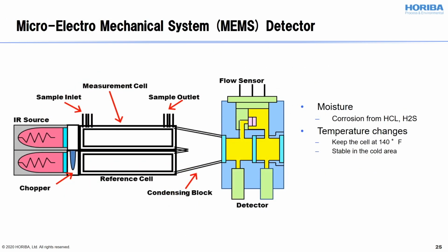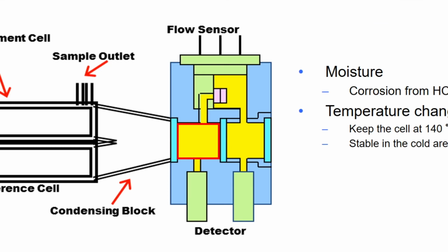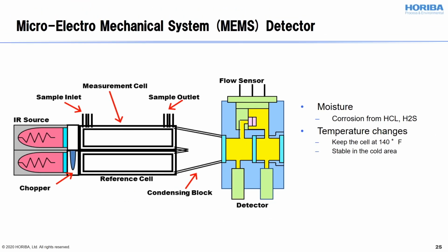Here is how NDIR works. The sample gas flows in and out of the sample cell, and the IR light alternately radiates through the sample cell and the sealed reference cell, controlled by a chopper. The gas being measured absorbs IR energy in the sample cell. This reduces the pressure inside the chamber in this detector. The detector gas flows from the second chamber to the first chamber because the first chamber's pressure is reduced. The flow sensor right here measures how much flow occurred, and the amount of gas flow from the second chamber to the first chamber is related to the gas concentration.